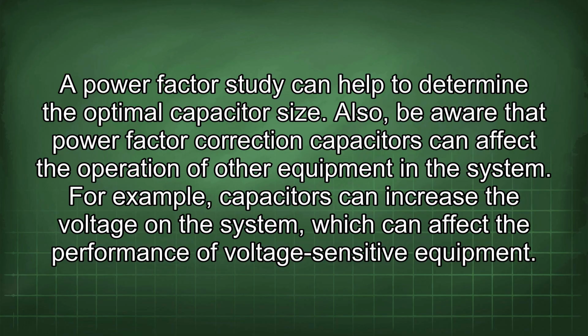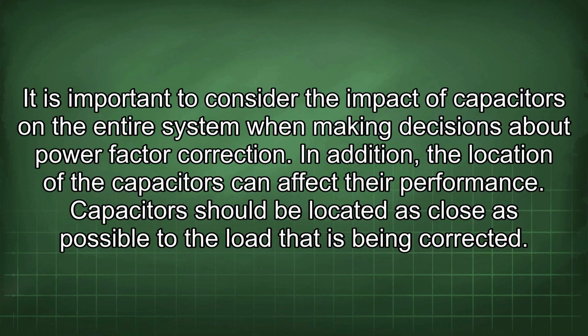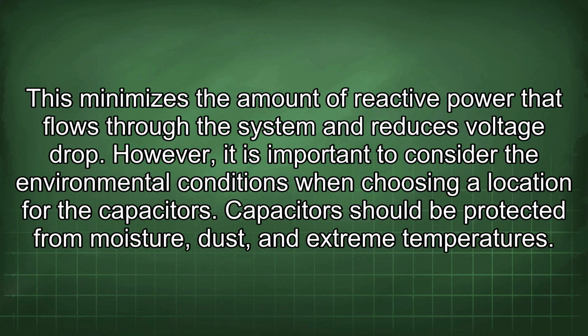Also, be aware that power factor correction capacitors can affect the operation of other equipment in the system. For example, capacitors can increase the voltage on the system, which can affect the performance of voltage-sensitive equipment. It is important to consider the impact of capacitors on the entire system when making decisions about power factor correction. In addition, the location of the capacitors can affect their performance. Capacitors should be located as close as possible to the load that is being corrected. This minimizes the amount of reactive power that flows through the system and reduces voltage drop.